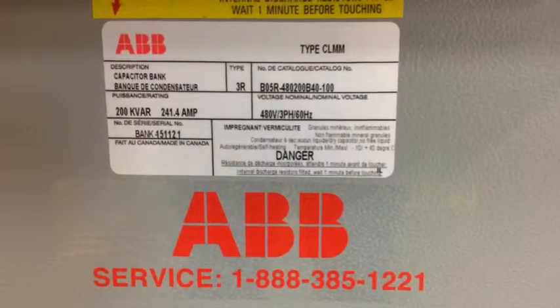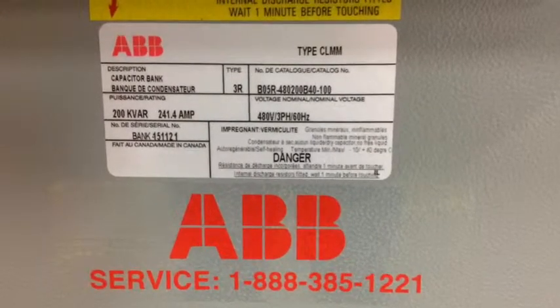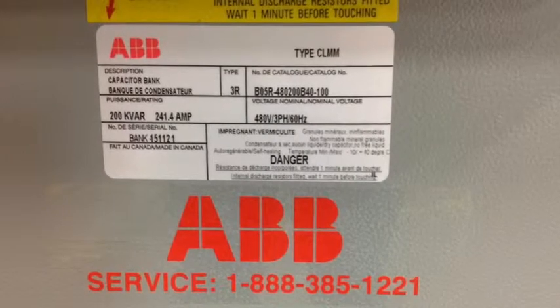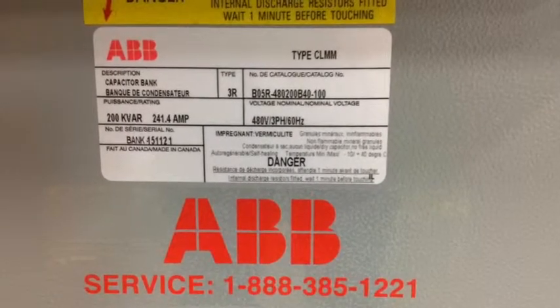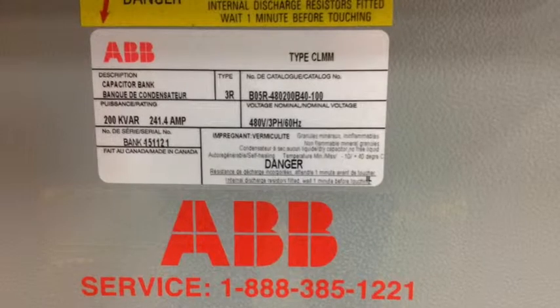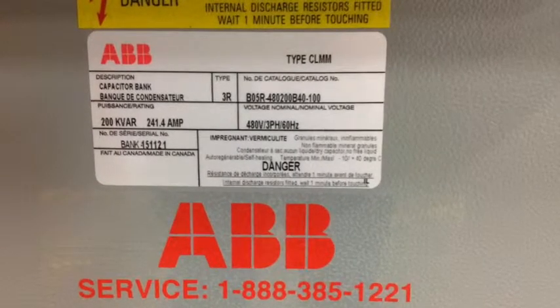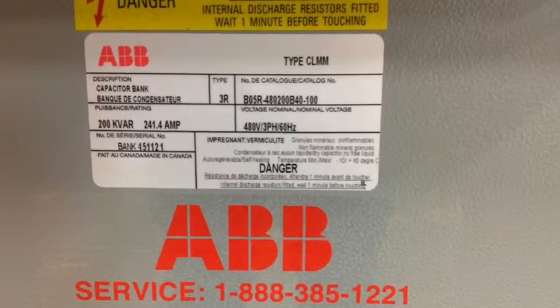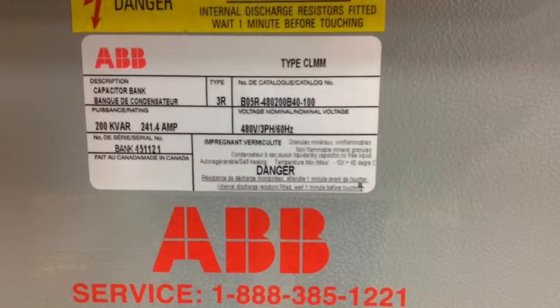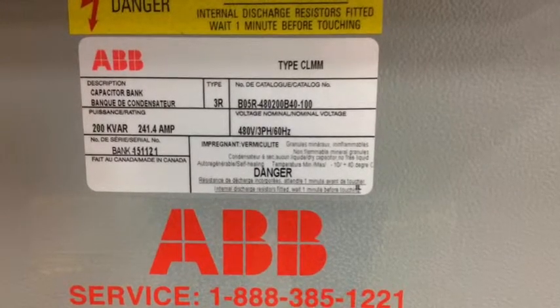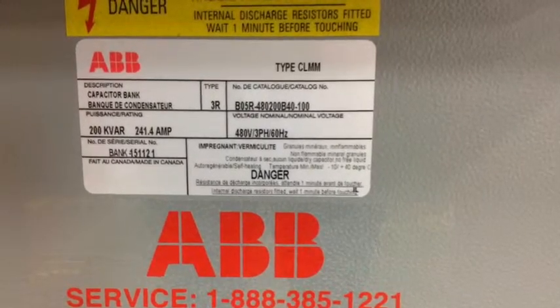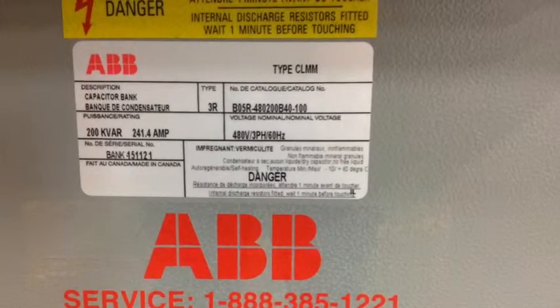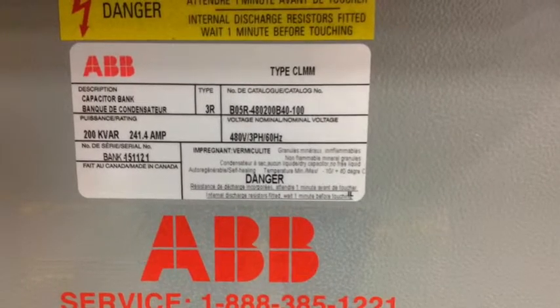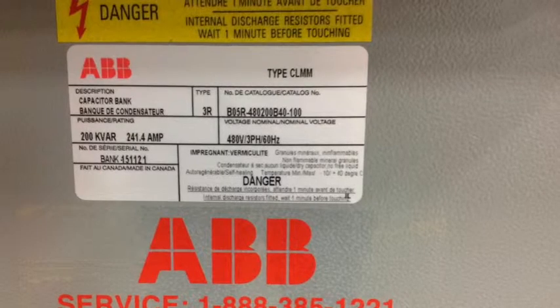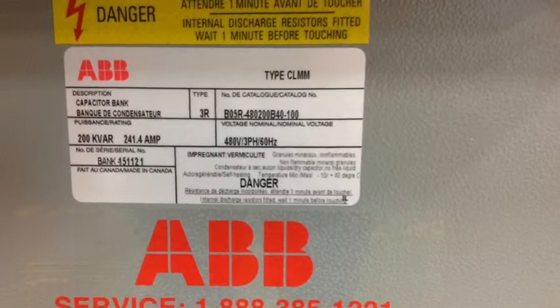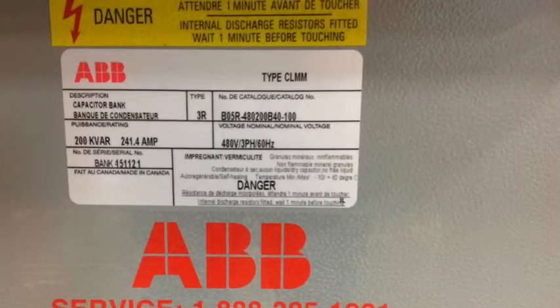This chiller was also provided with a power factor correction capacitor bank. We utilized ABB to provide the power factor correction capacitors. This module will be separate from the chiller and provided by Multistack for installation by the contractor in the electrical distribution system. The power factor correction capacitors will improve the chiller's power factor to overall improve the building's power factor.